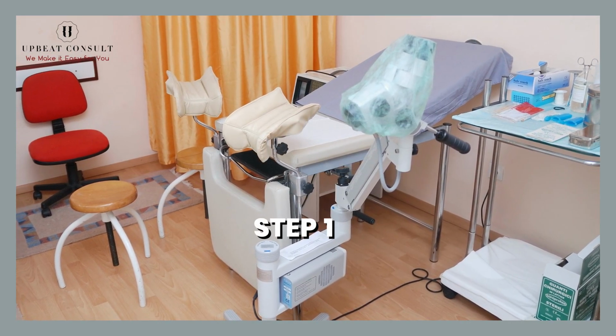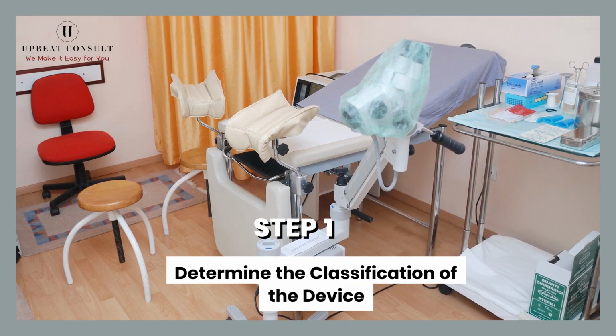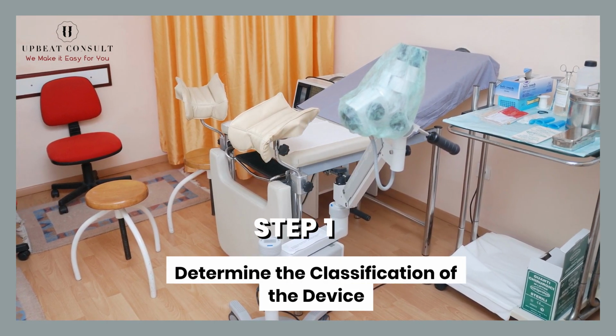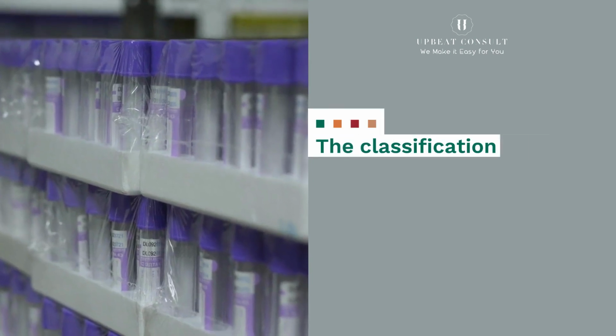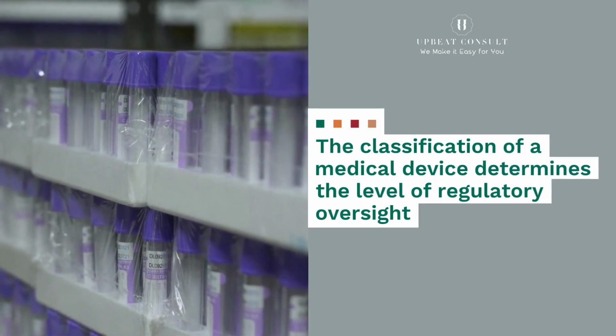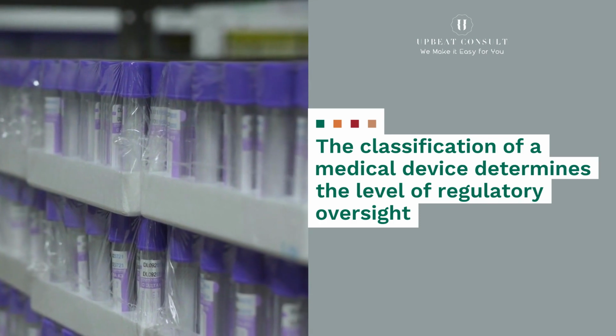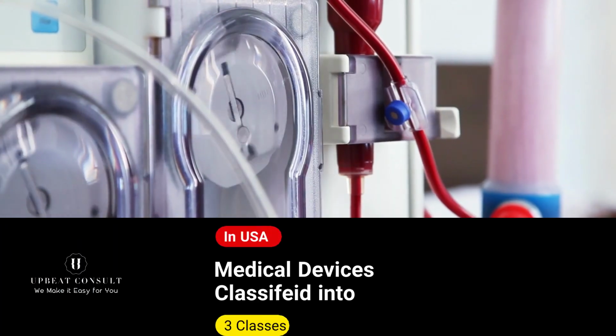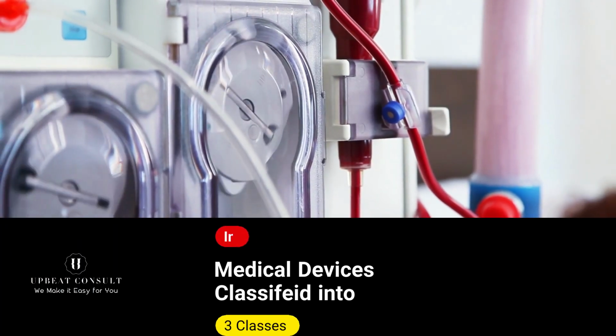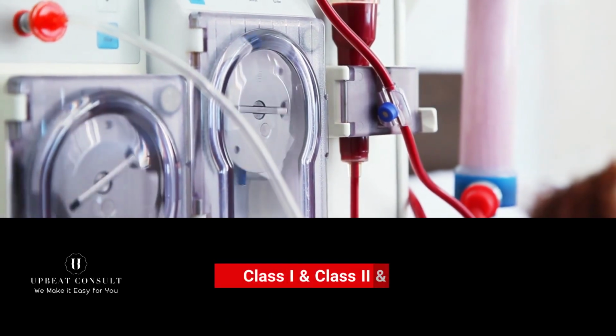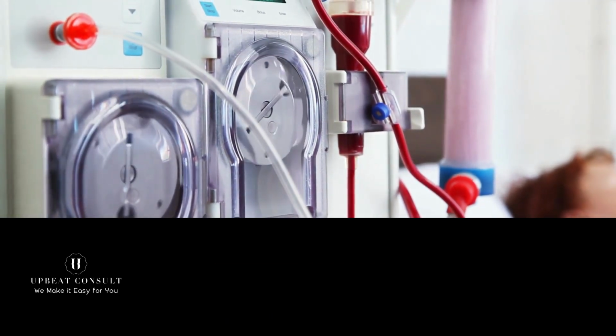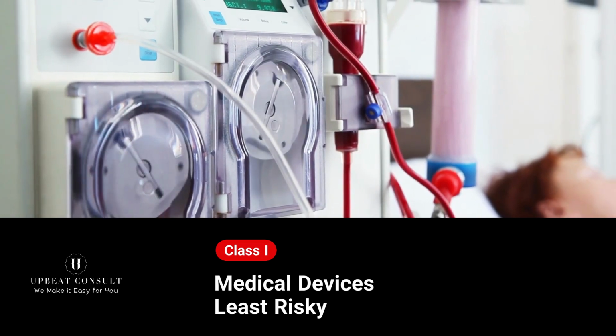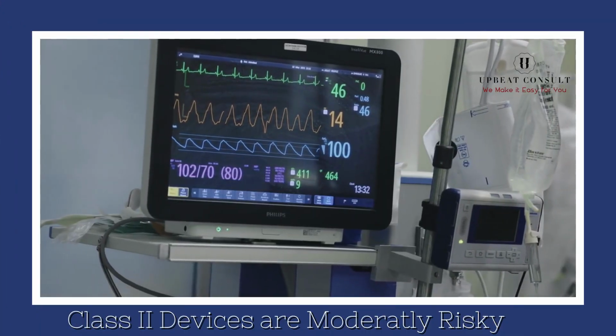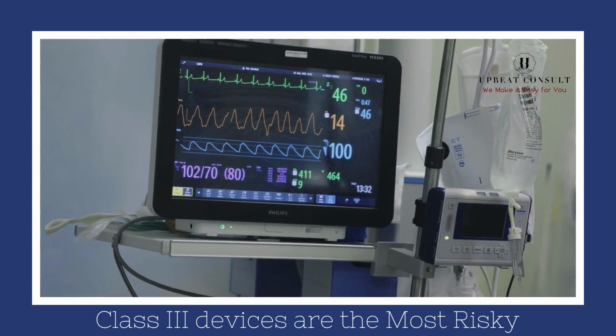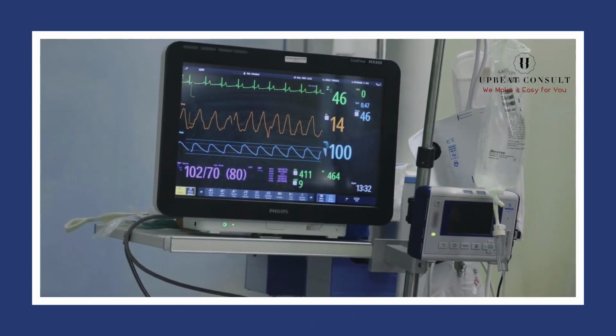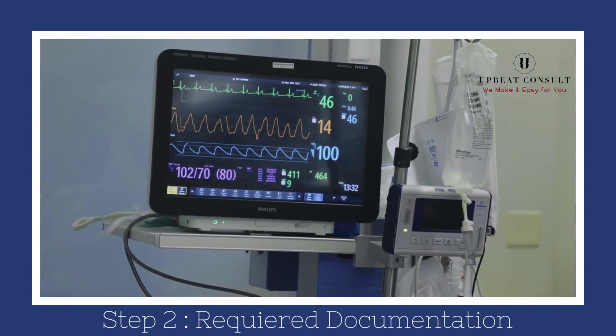The first step in registering a medical device is to determine the classification of the device. The classification of a medical device determines the level of regulatory oversight that it is subject to. In the United States, medical devices are classified into three classes: Class 1, Class 2, and Class 3. Class 1 devices are the least risky, Class 2 devices are moderately risky, and Class 3 devices are the most risky. The next step is to gather the required documentation.